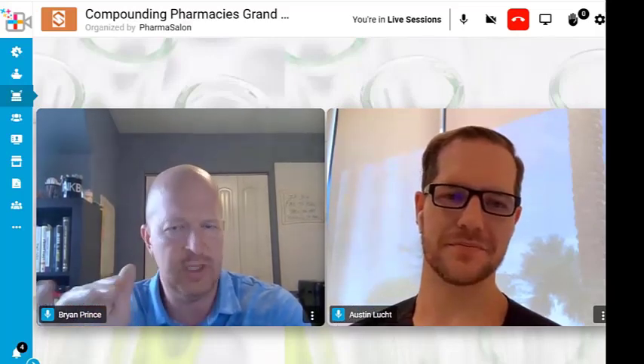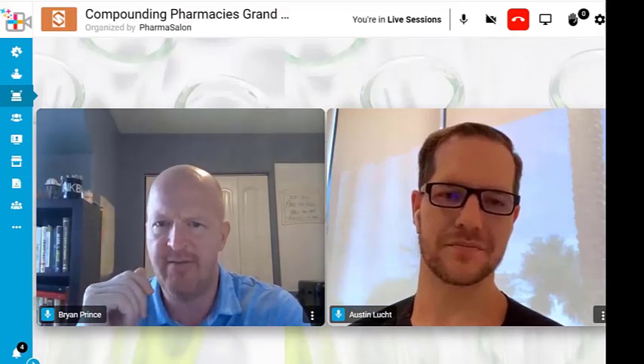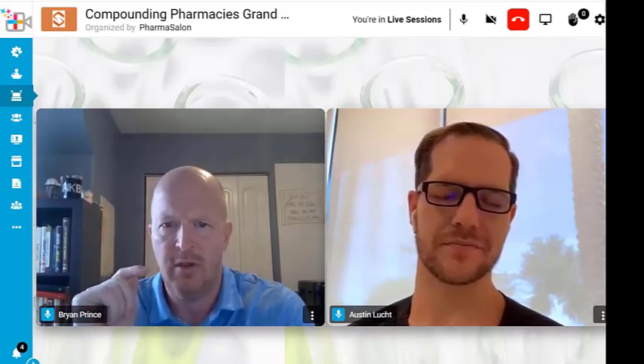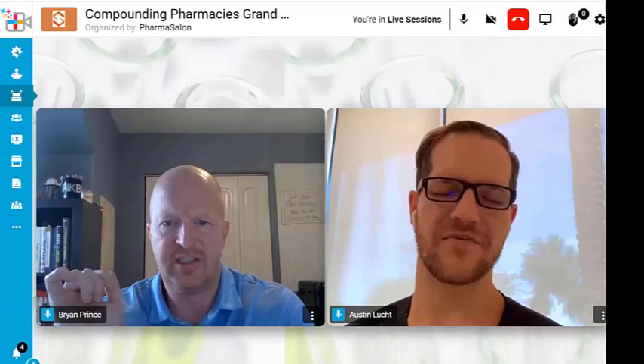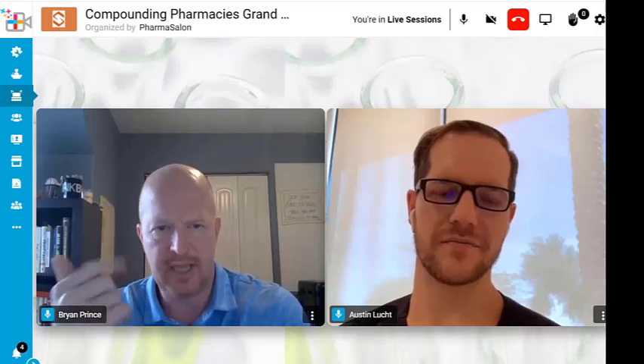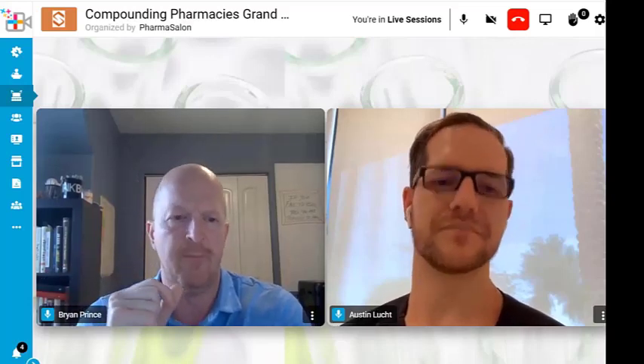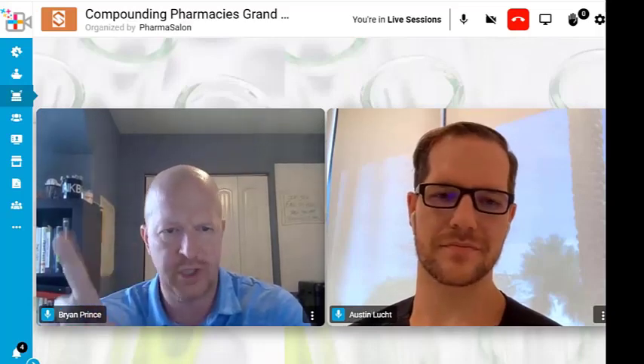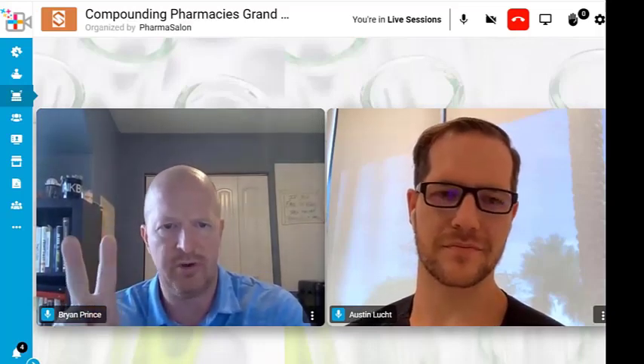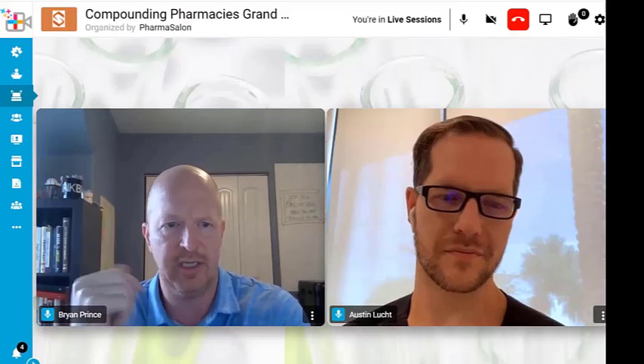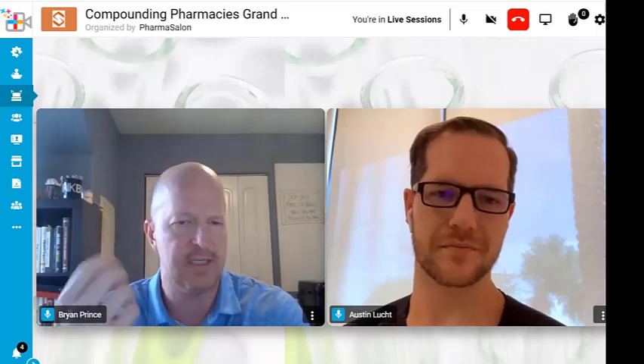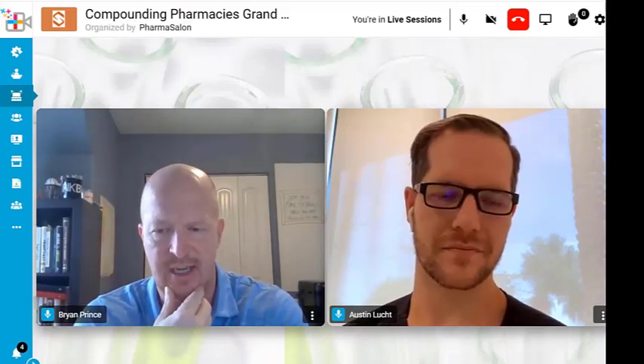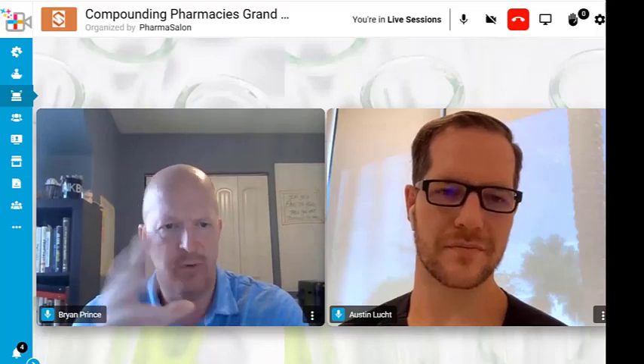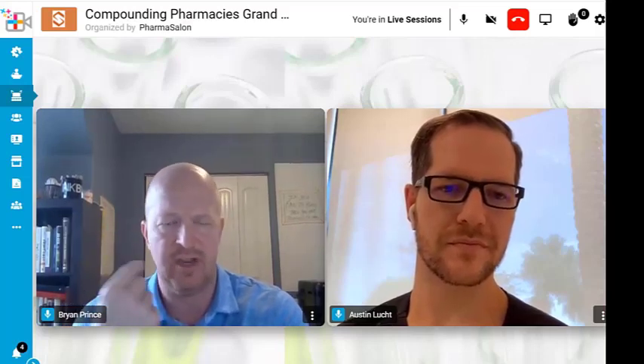So one of the things that I did for Alston, and I was his engineer really, is there were so many different rooms within your clean room, Alston. I think there were seven, one, two, three, five. Five rooms, but kind of a different little corridor space as well. And we engineered everything on what's going to return, what's going to exhaust, at 45 air changes, the entire clean room, even though you can have an ante room as an ISO 8, we actually designed it as an ISO 7. So for various PPE reasons and stuff like that.